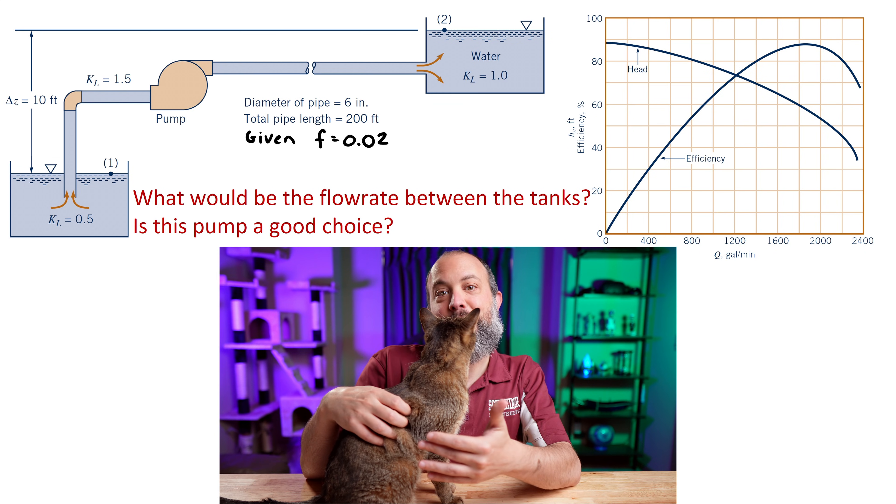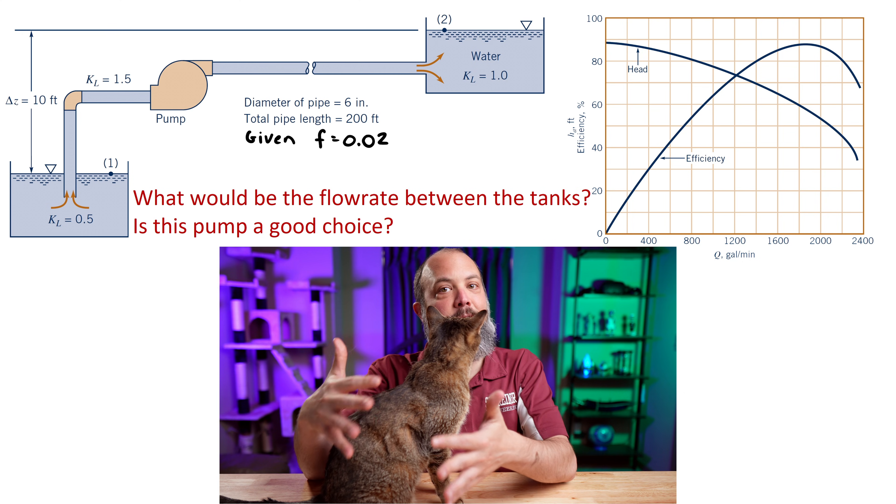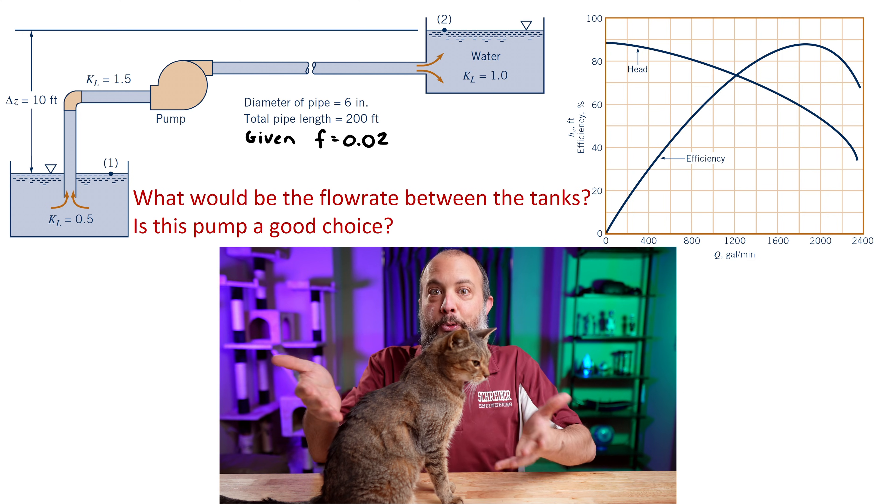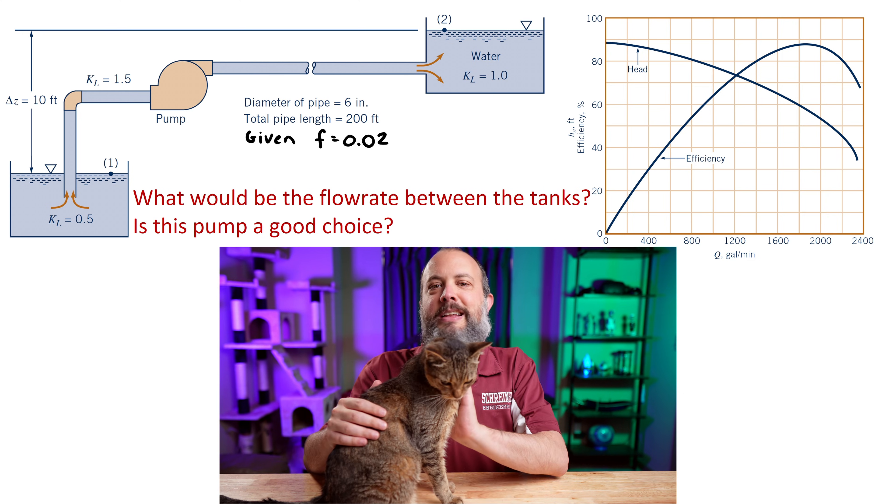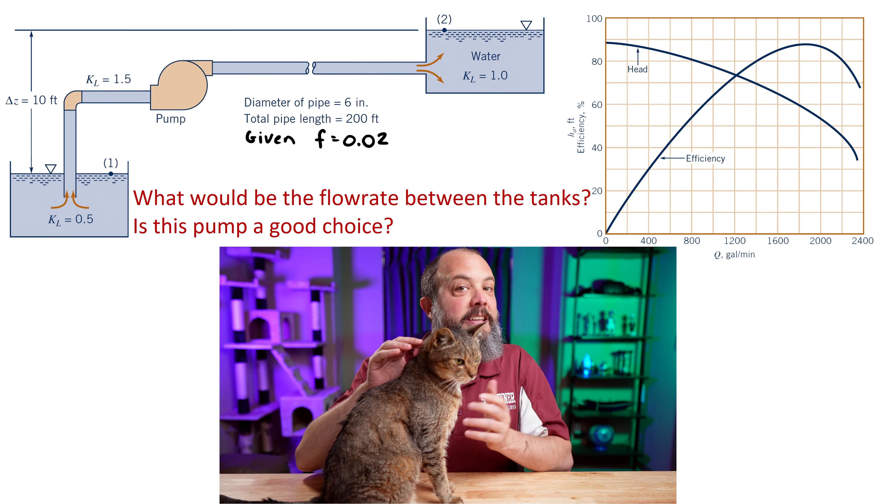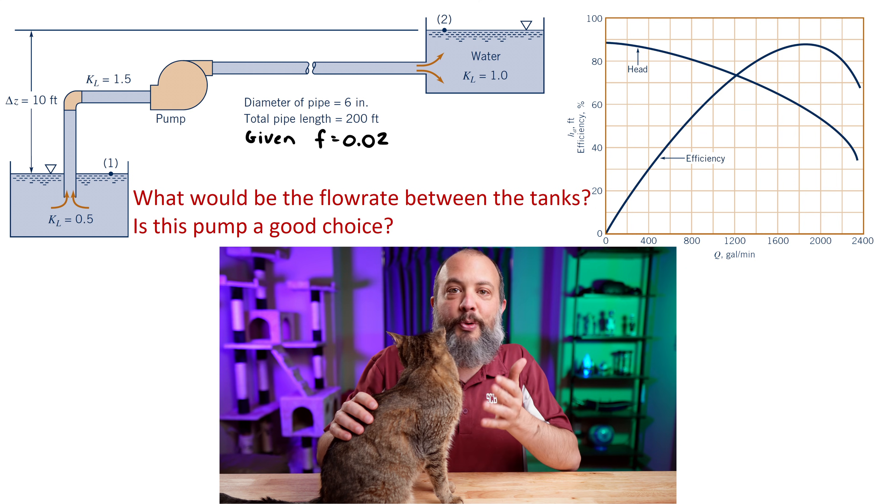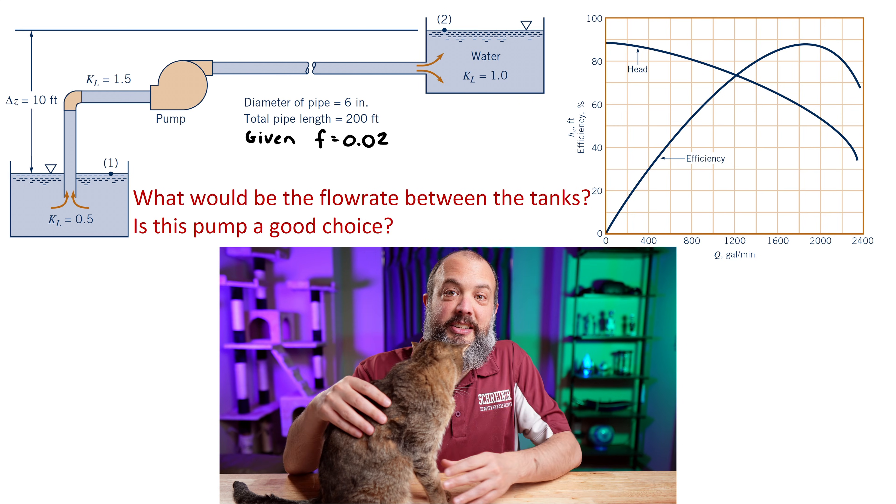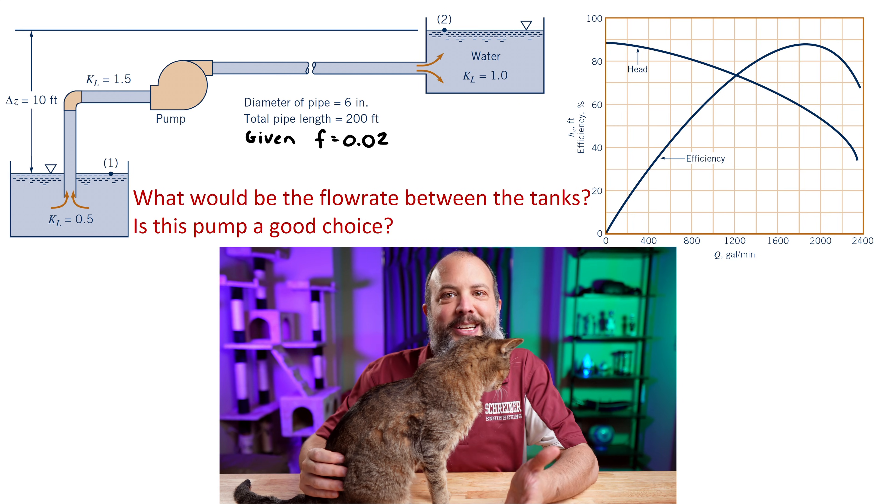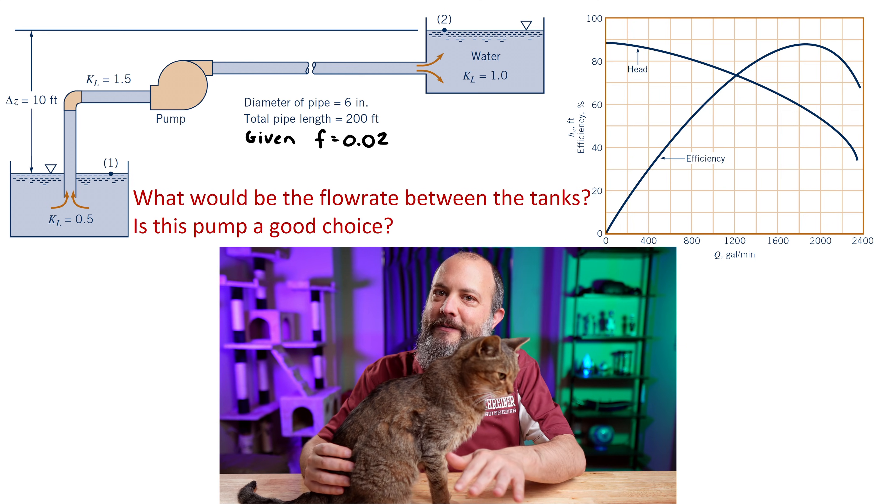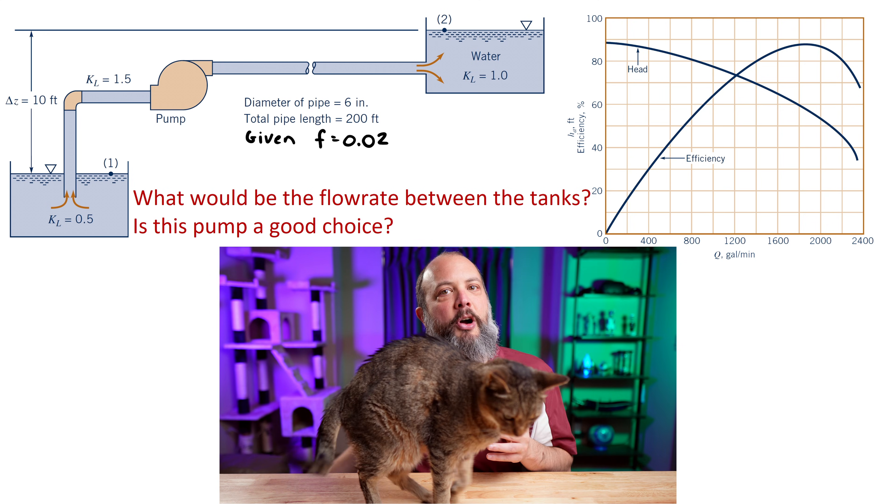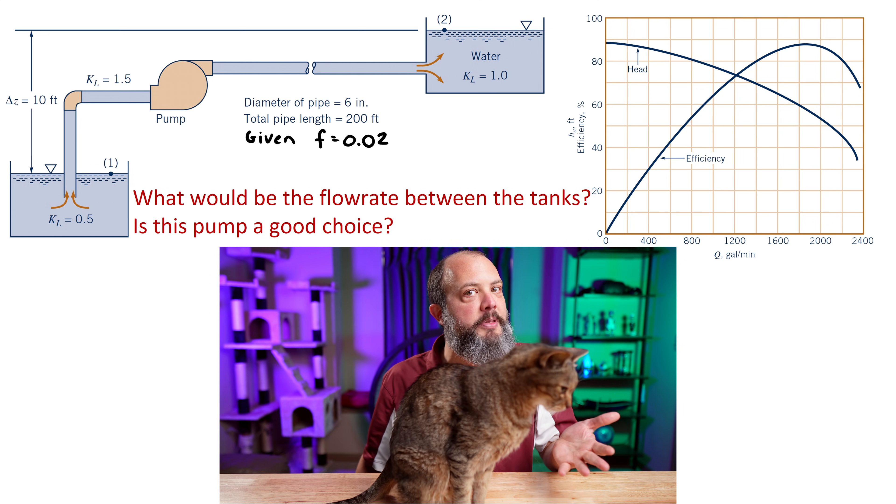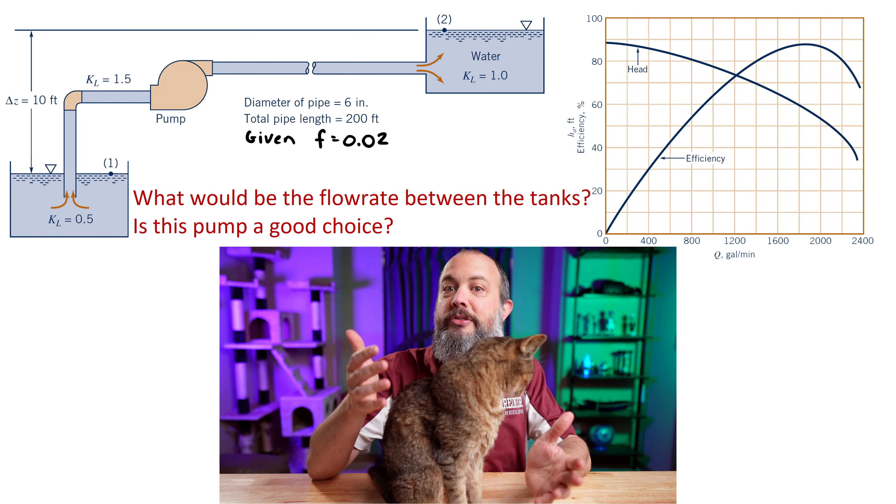And to evaluate whether this pump is a good fit, you'll just check whether or not that's actually the flow rate that you want for your system. And if you're given a pump curve like this one that has efficiency listed, you'll check as to whether the pump is actually behaving at or near its peak efficiency, since efficiency will be related to electricity bills.